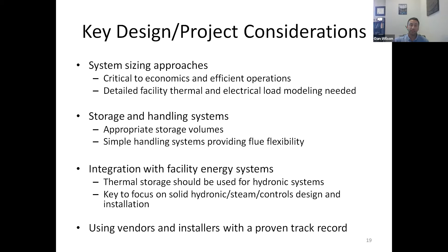The first thing and the most important step in any wood energy system evaluation is detailed load modeling. And until that's done, really not worth spending a ton of time on sizing systems. Really, you should focus your efforts on load modeling for the chillers, or for the cooling load, thermal load, and the electric load, and then you can get into sizing. Once you've done that, and here we're showing with this blue line a daily average steam demand for a campus, once you have that load model done, you can size a system.